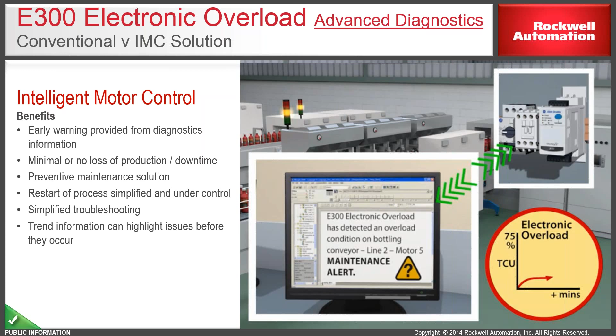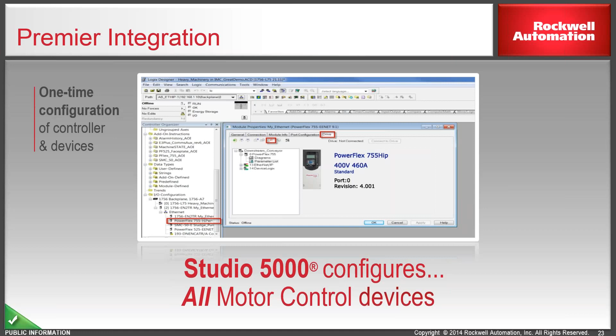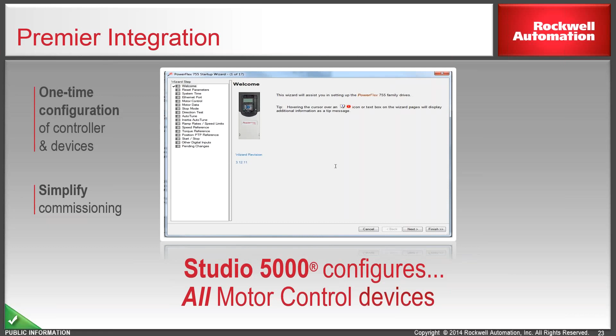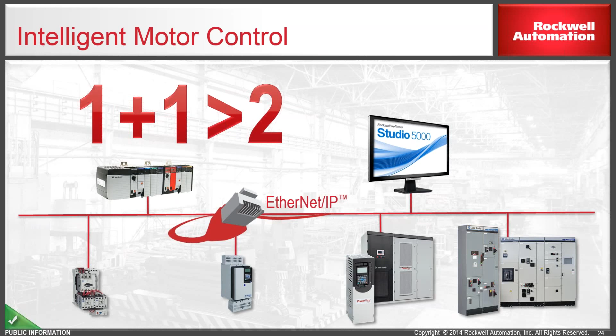So premier integration, this I talked about, how to configure the relays. We have Studio 5000, which configures all motor control devices, right? It's a single software, and this is how it looks on Logix Designer. It's a one-time configuration for the controller and devices. You don't need a different software to configure different motor control devices. The commissioning is simplified for the engineers. So intelligent motor control now gives you significant improvements because all your devices are connected on Ethernet IP. You have a single software, Studio 5000, configurable for your controllers and all your motor control devices, so it is Ethernet IP enabled. For more solutions, these are some of the customers to whom we have supplied intelligent motor control solutions.